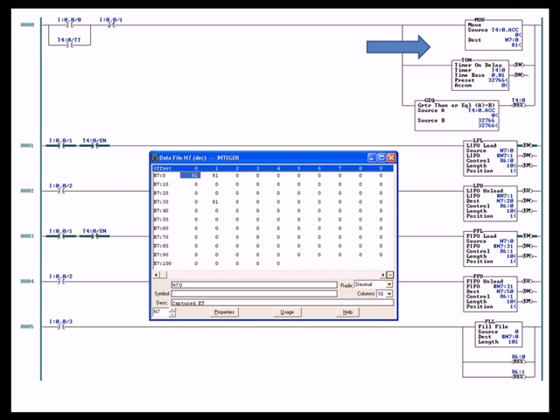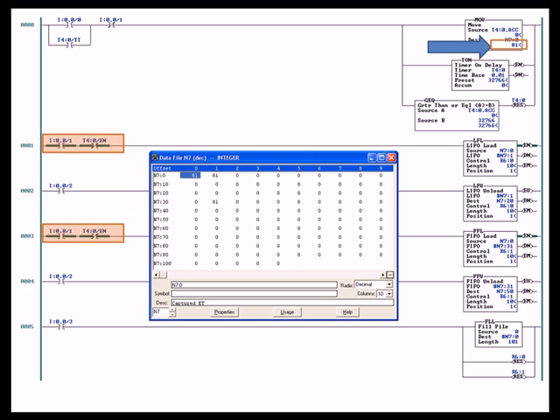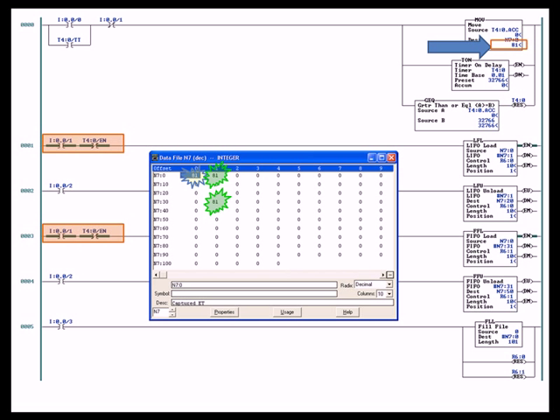We flip that switch on, which rung 0 now becomes false and resets the timer. Now that this rung is false, the move instruction will no longer be moving a value from the accumulate T4:0 into N7:0. Rungs 1 and 3 are now true, so they would immediately execute the LIFO load and the FIFO load. The value that is in N7:0 would be moved to the address for the LIFO, which is N7:1, and the address for the FIFO, which is N7:31. And you can see in our illustration here that N7:1 and N7:31 are now equal to N7:0. That might not be 81, it just depends on where the timer accumulate was at and its value when you turned on switch 1, which makes rung 0 go false, rungs 1 and 3 go true.